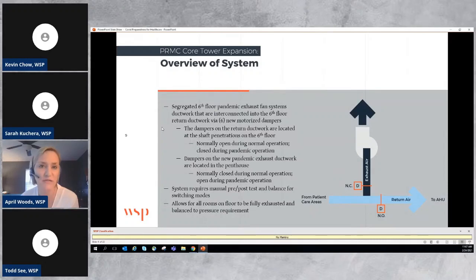However, we were still able to keep the rooms that had special pressure relationships, like a clean supply room, to still maintain positive pressurizations. So with this strategic motorized damper operation, rather than returning the air back to the unit, we were able to close that damper and open the damper that would then go to the exhaust fan. Something that is important to note is that it does require a manual pre and post test and balance every time they want to switch the modes, which hopefully is not often.